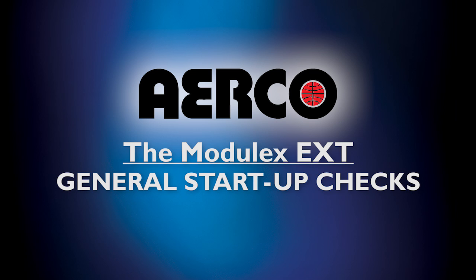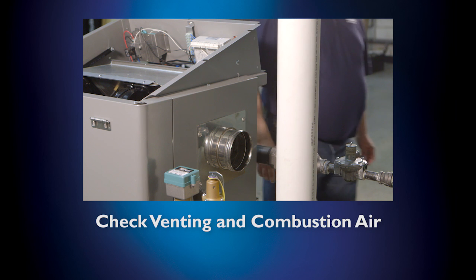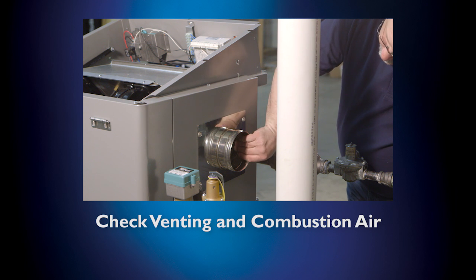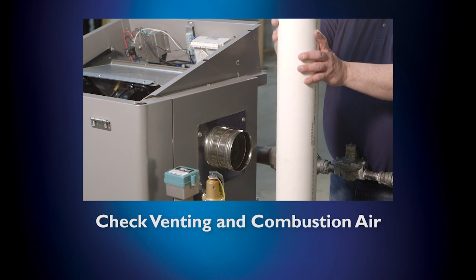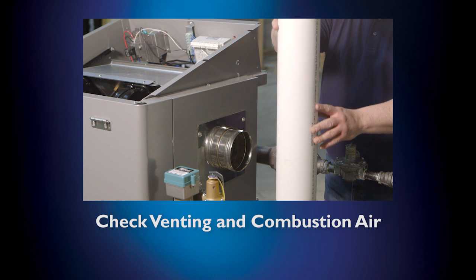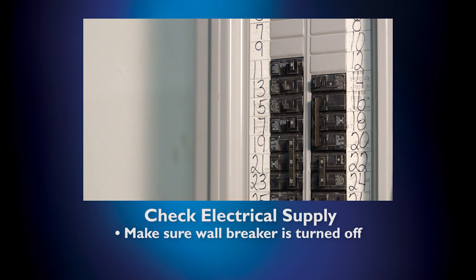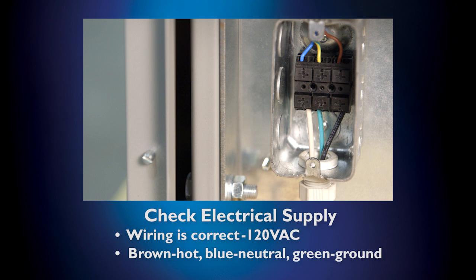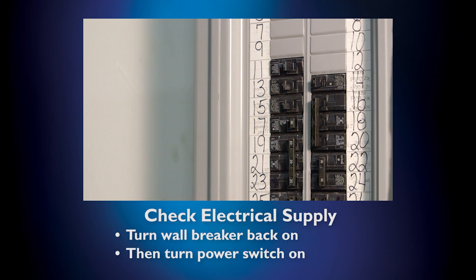Your boiler has been installed using specific requirements and specifications that are in accordance with your unit's manual. First, check your unit to make sure the combustion air inlet and the discharge of combustion exhaust occur correctly, meaning they are in alignment with your unit's manual and its specific standards. Next, check your unit's electrical supply. Begin by making sure the wall breaker is turned off. Then, check to make sure the wiring on your unit is correct. This means the hot side of the 120 volts AC, or the black wires, is tied to the brown wires. The neutral side, or white wires, is tied to the blue wires, and the ground wires are connected to the green wires in the unit, all as shown here. Once you've checked that all the wiring is correct, turn on the wall breaker and then turn on the unit's power switch.